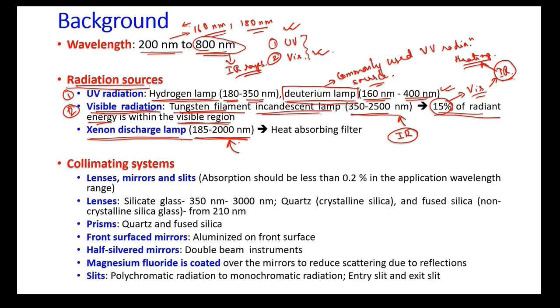The visible radiations generated by the tungsten filament incandescent lamp and the xenon discharge lamp have a large portion in the IR radiation range, so we have to use heat-absorbing filters to prevent too much heat being generated within the enclosure of the UV-visible spectrophotometer. The take-away is that current-day UV-visible spectrophotometers usually use the deuterium lamp (also called D2 lamp) and tungsten filament lamps for research-grade instruments.